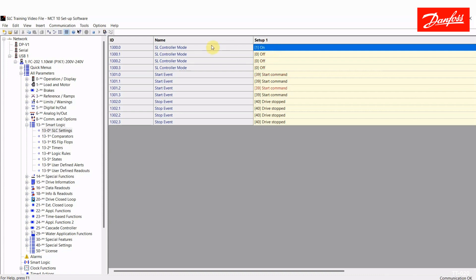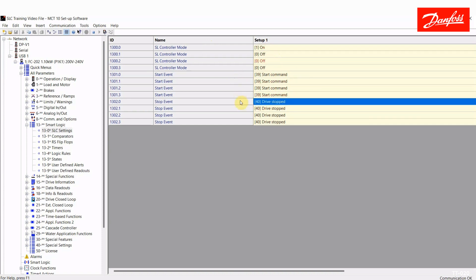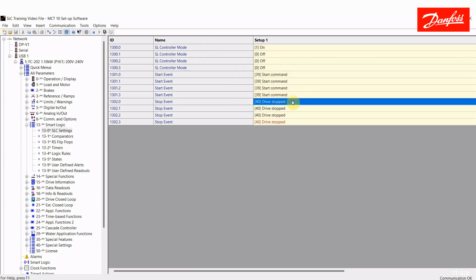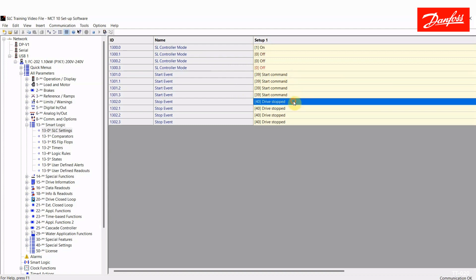It'll be easier to understand, but if you just want to use various rules such as a comparator or a logic rule and attach that to a physical output, you do not have to have the controller set to on. So if you do want to execute a sequence, you need to have the controller set to on, and then you choose a start and a stop event. Now by default, it's set to start command for the start event, meaning any time that drive receives a start command, you would go into the program sequence. This basically means that you're living in the controller any time the drive is running.